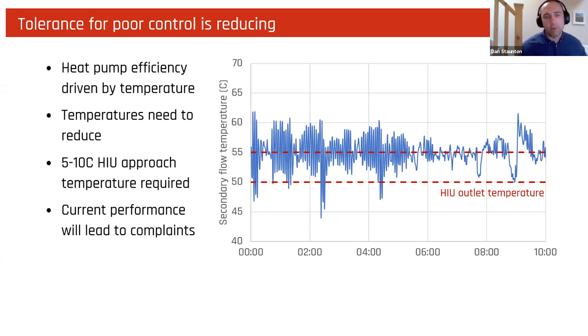If we overlay, like we have done on the right-hand side here, the current levels of stability that we see, this is a fairly common level of stability. We haven't picked out a particularly poor plate heat exchanger. You'll see that if we're trying to maintain a 5 degree approach temperature, we can't do that. So our current approach, our current designs, our current controls don't provide adequate stability for us to maintain comfort, domestic hot water and space heating continuously.